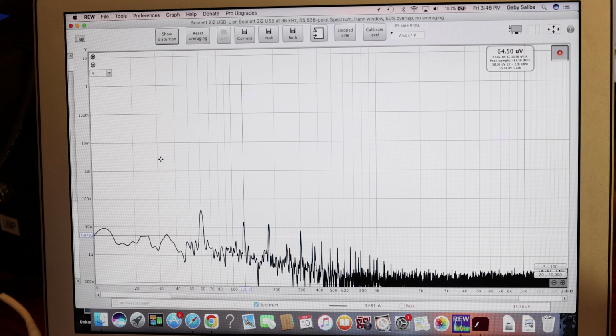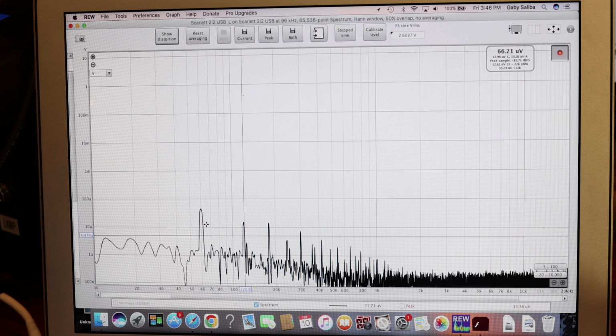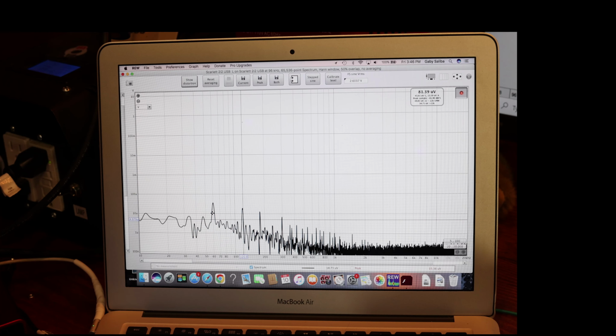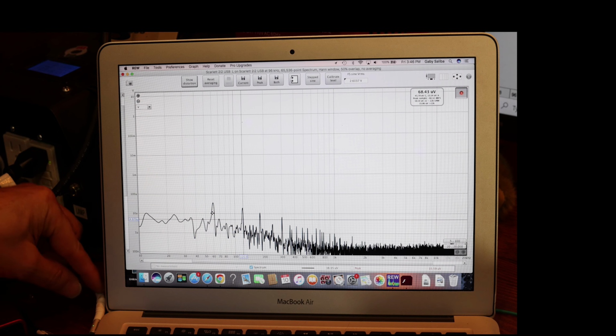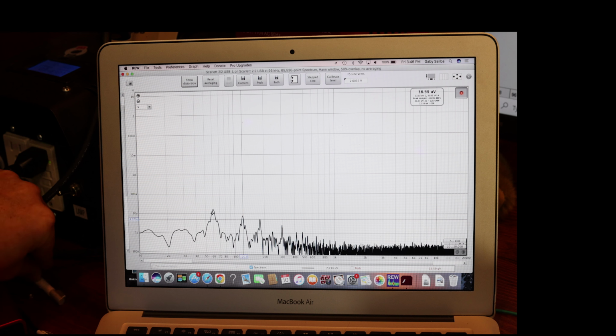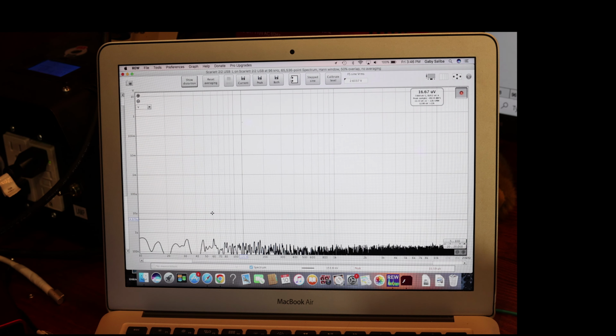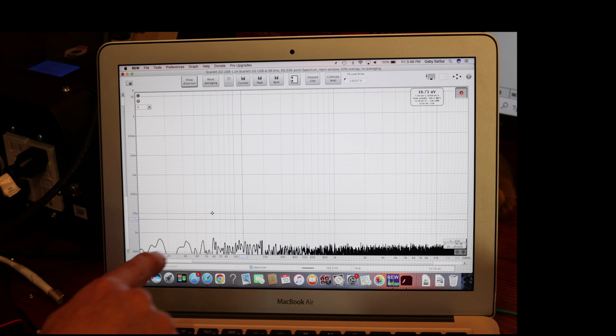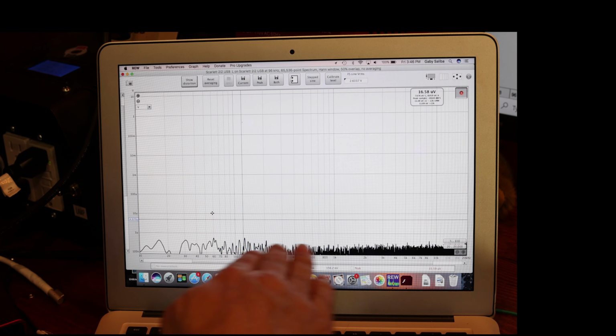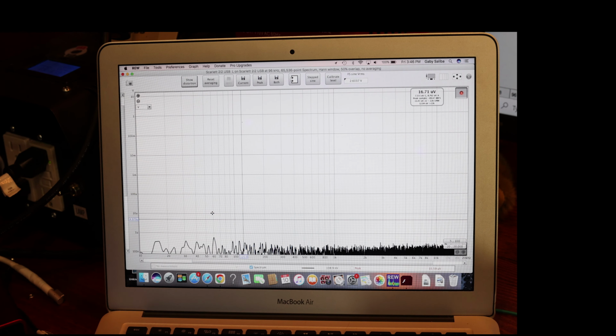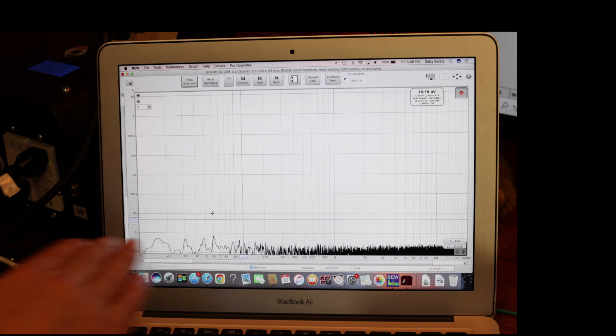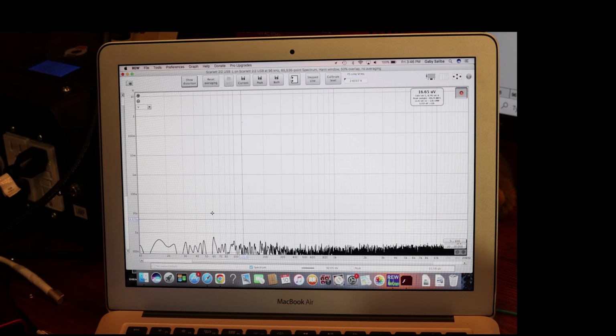And now the reason the noise is higher is that this computer is still plugged into the power. If I unplug it, notice how the sound is going to get much lower. We are down to half a microvolt of noise, so very safely up to 1 microvolt. Now we can basically test equipment up to about half a microvolt of sensitivity.